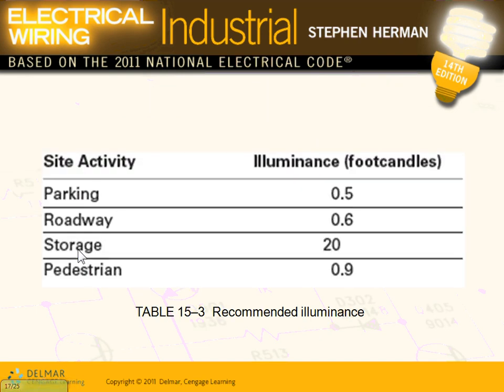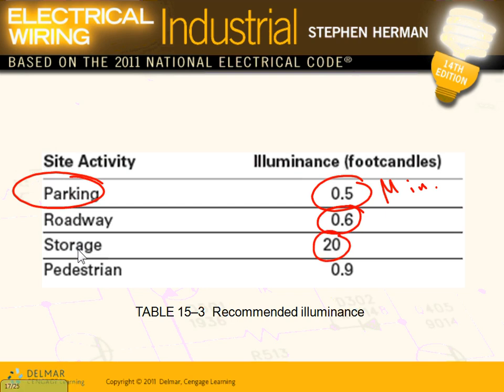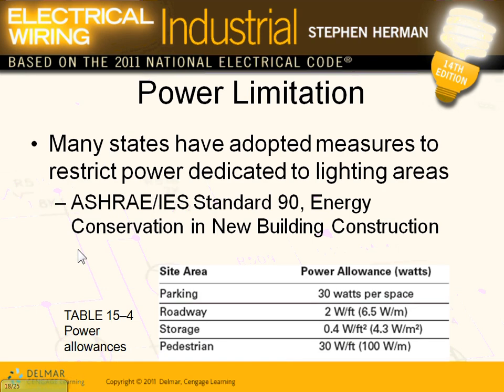Open that IES file, get all the information about the lumens and the fixture, drop the lumens on the floor — lumens over area becomes foot candle — and that's how you get your minimum, maximum, average, and average-to-minimum. Here are some recommendations. The minimum is 0.5 foot candles — enough for you to walk and find your car, not to read a newspaper. These are IES recommendations in the Visual software. Because we're becoming environmentally friendly, we need to maintain power limitations with ComCheck and ASHRAE standards.